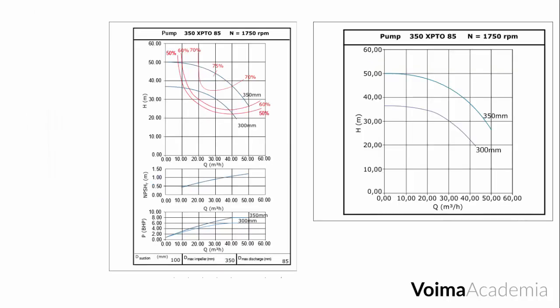Here is a typical chart containing the characteristic curves of a pump. Usually, these charts present the head versus flow curves for the maximum and minimum impeller diameters that this pump can contain. In another video, we saw how to obtain the head versus flow curves of an intermediary impeller. Also, in another video, we saw how to obtain the power curves demanded by the pump.